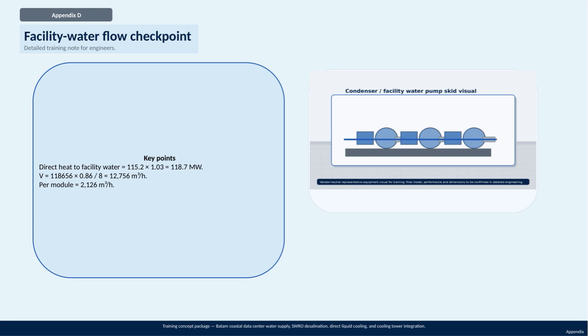One of the key points here is the calculation of direct heat to facility water, which comes out to 118.7 megawatts after applying correction factor. This heat load determines a volume flow rate required to effectively manage cooling. Using the formula provided, the total flow volume calculates to about 12,756 cubic meters per hour. Breaking it down further, each module within the system handles around 2,126 cubic meters per hour, ensuring efficient distribution and cooling capacity across the facility. This detailed checkpoint is critical for engineers to understand flow requirements and design considerations within the integrated cooling systems.